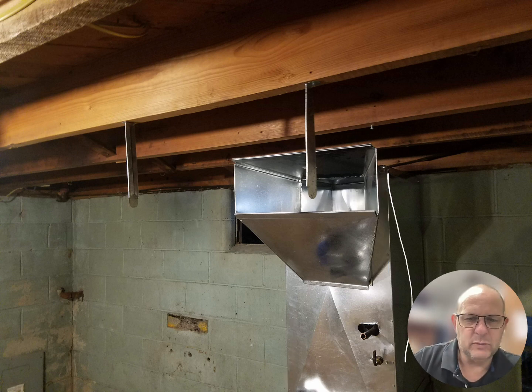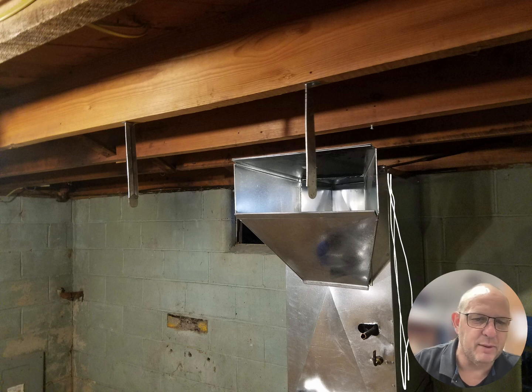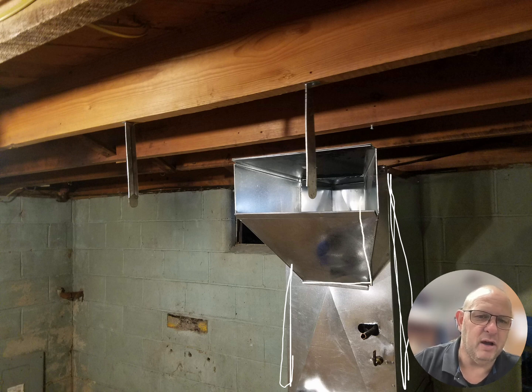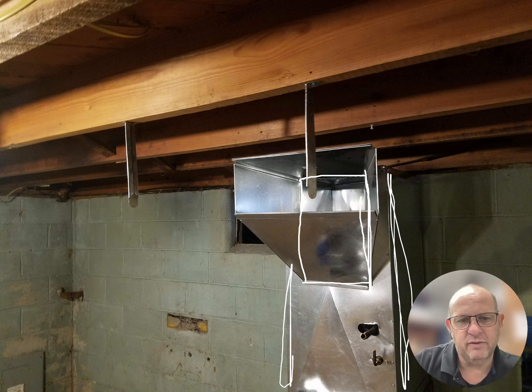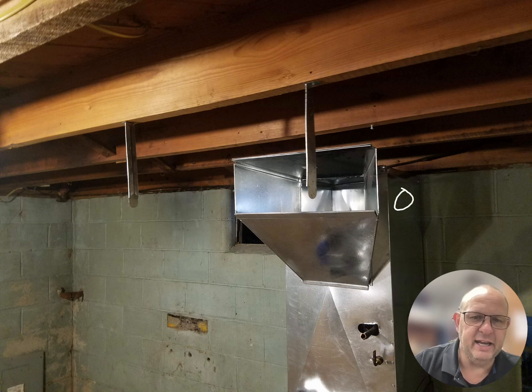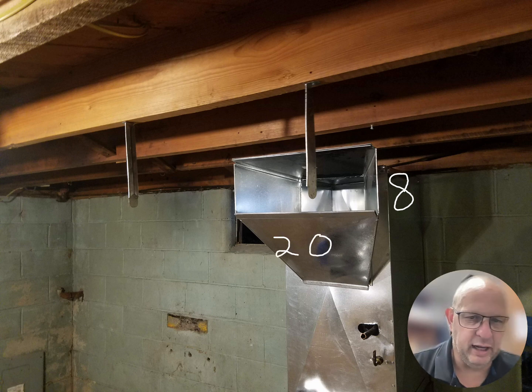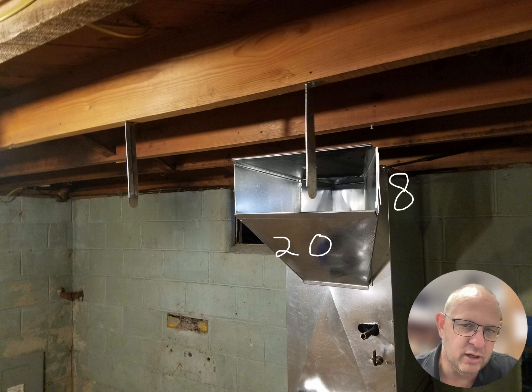So here's our plenum. I talked about numerous different types of takeoffs that we will see on our systems. This one happens to be a transition type of takeoff. And if I was to draw this on the inside, we would see that the transition goes from a rectangular type of ductwork into what we like to look at as our 8-inch by 16, or this one just happens to be 20 inches in length. So that is a transition type of ductwork when we look at it. Our drive cleats will fit on the shorter side. Our S-lock will be on the longer side.